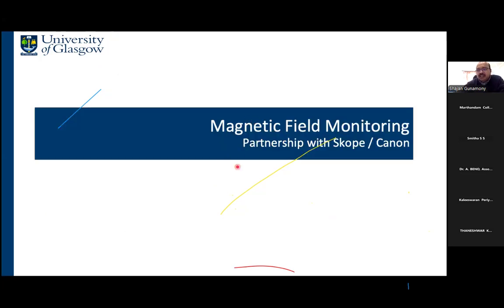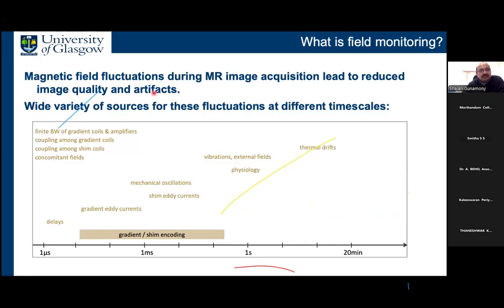Right, so I want to introduce another small topic called magnetic field monitoring. What exactly is magnetic field monitoring? It means that there are magnetic field fluctuations during an MR image acquisition, which lead to reduced image quality and artifacts. There are a wide variety of sources which can cause these fluctuations. For example, if we are scanning for a long time, let's say 30 to 40 minutes, all the electronics in the scanner and also the coils and everything heats up. This can cause drifts in the magnetic field.